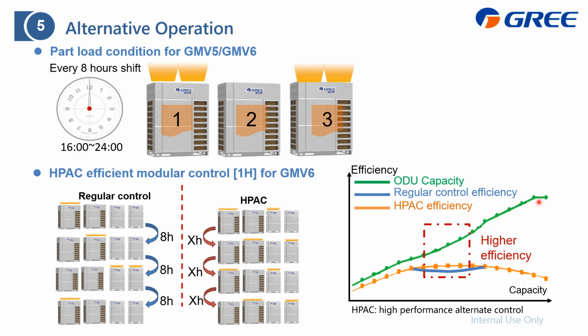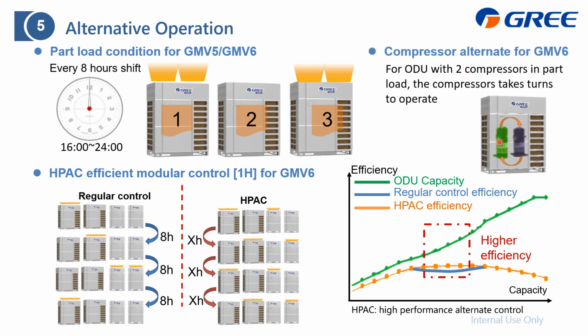When the outdoor unit capacity is lower, which also means the part load condition, the efficiency will also go higher. However, in this area, the outdoor unit capacity is lower, but without HPAC the efficiency will not become higher and will follow this blue line. The reason is the compressor is not at its best working zone. So to ensure this, we need to set up this HPAC. Then after you turn it on, we can raise this efficiency. Not only for the whole outdoor unit, but for an outdoor unit with two compressors, we can also balance the operating time between these two compressors. This is only for GMV 6.